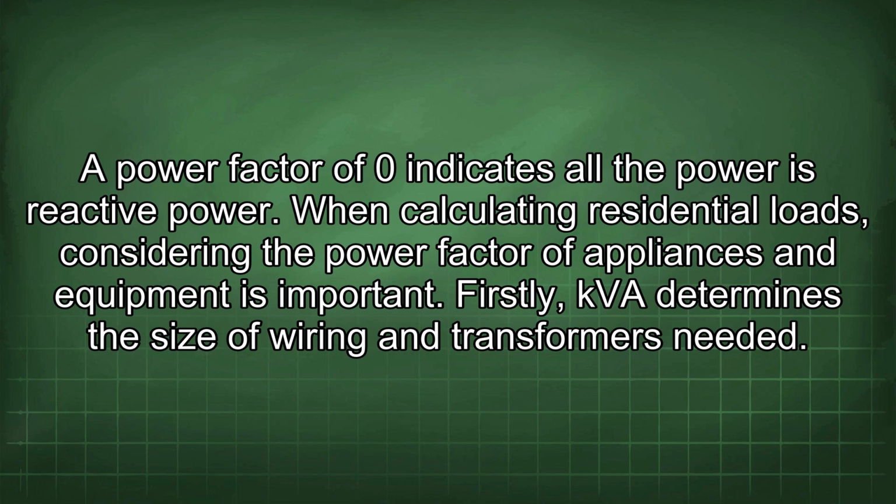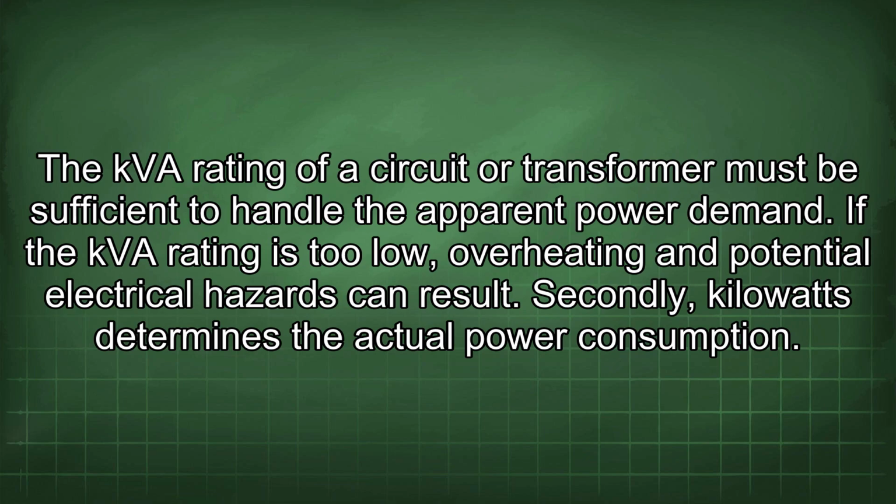When calculating residential loads, considering the power factor of appliances and equipment is important. Firstly, KVA determines the size of wiring and transformers needed. The KVA rating of a circuit or transformer must be sufficient to handle the apparent power demand. If the KVA rating is too low, overheating and potential electrical hazards can result.